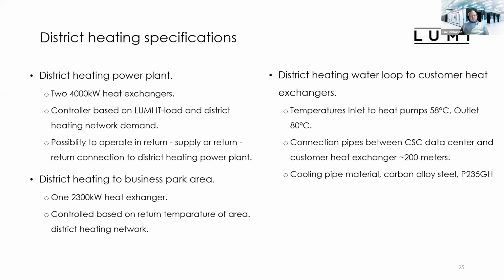So we can take a side flow from the return side of the district heating network. So from the city's incoming cold temperature, we are preheating that to 80 degrees, and we can push it directly to the district heating network, or we can push it to the district heating power plant. So we are preheating their production, so they can adjust their own production based on how much preheating we do for the district heating network.